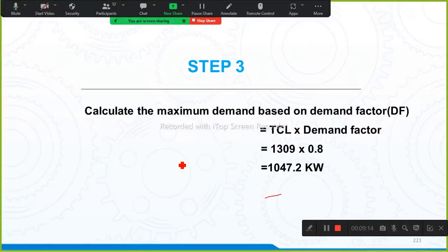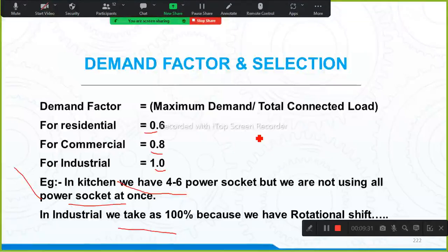Now when I took this as a commercial building, what is the demand factor for a commercial building? 80%. So 1309 ka 80%, the load is 1047.2 kilowatt. This is the MD. Maximum demand is nothing but 1047.2 kilowatt is the maximum demand. Okay.